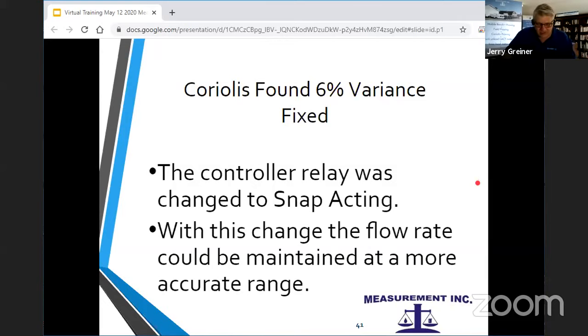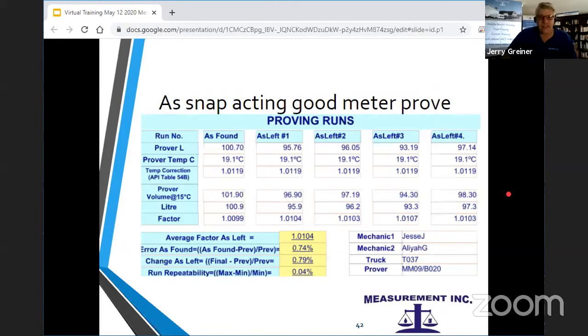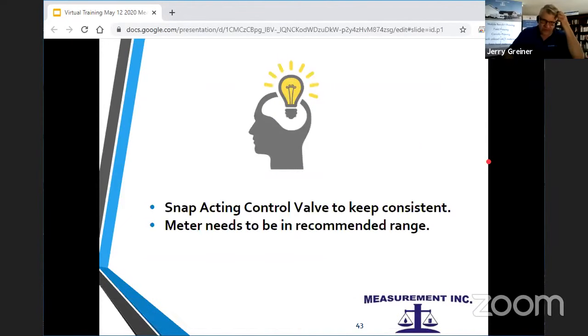Okay, next, we found this variance. We changed the controller to a snap acting controller, and then when we changed that, the flow rate was maintained in the more accurate range. As soon as we changed the controller, nothing else, we got then 4 runs. They were all dumping at a consistent range, and you can see a 0.04% repeatability between runs as soon as it was changed. So that was one of our things that we were able to learn as well.